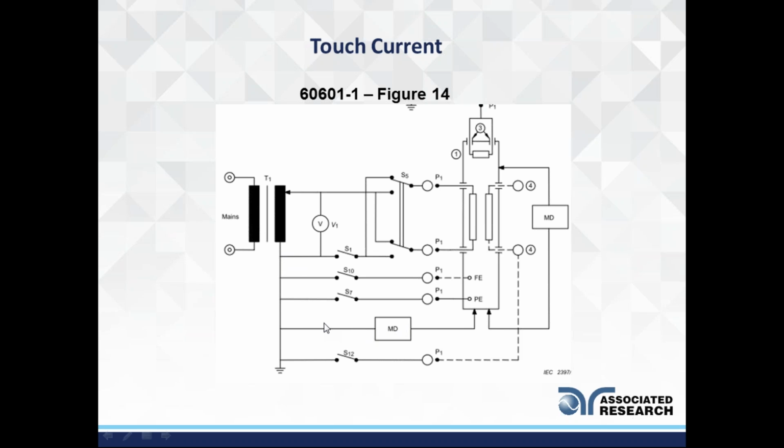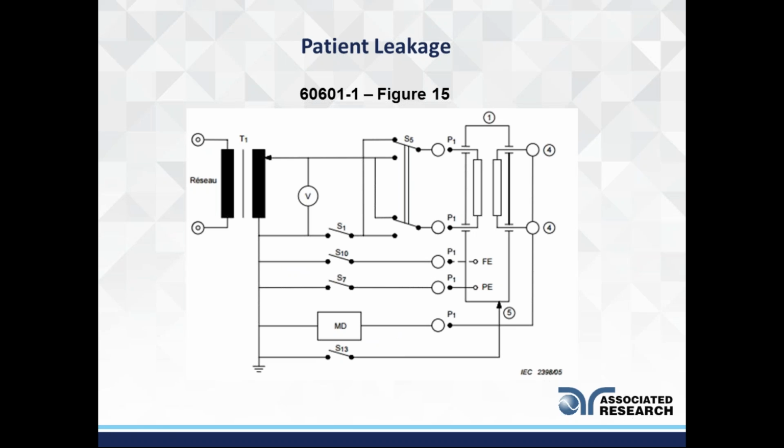So that's touch current. So now let's look at patient leakage. Very similar. I don't know if anyone can identify the only difference here. We still have, well, besides it's in French apparently, my input power. I still have my reverse polarity.